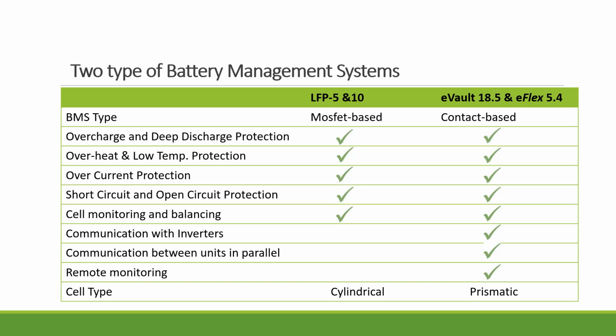The eVault and eFlex use a contact-based BMS, so you have a relay and a fuse there. They can handle much more charging and discharging current, as well as surge capacity. It covers everything the MOSFET BMS does, but in addition, it allows you to communicate with inverters and between batteries in parallel, as well as remote monitoring, which we're working on. That should be available in the next few months.